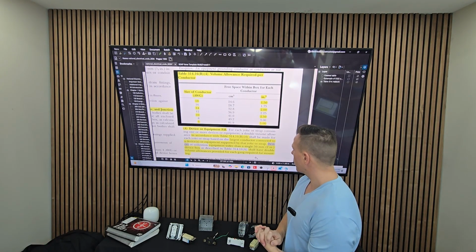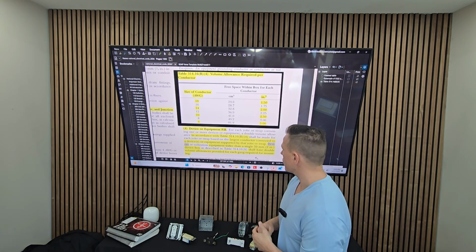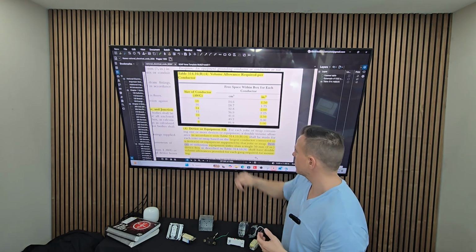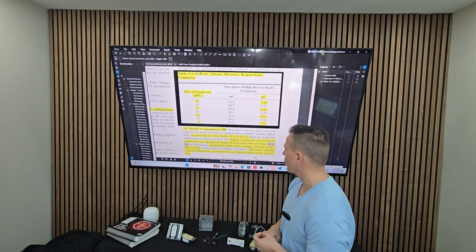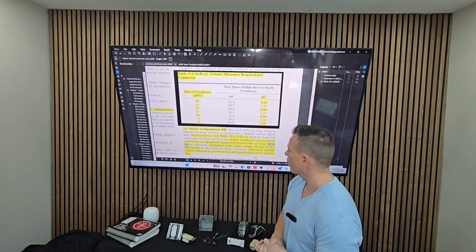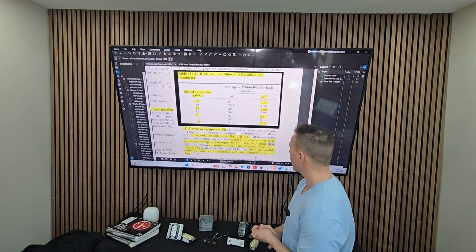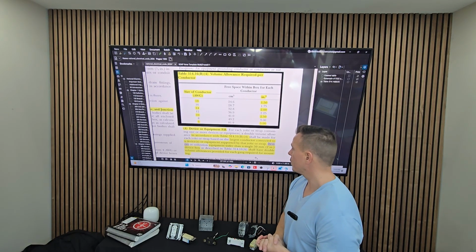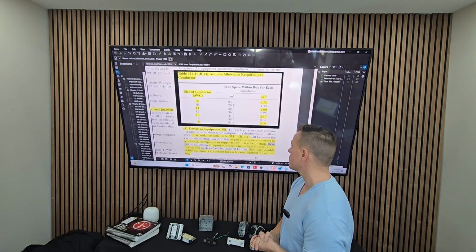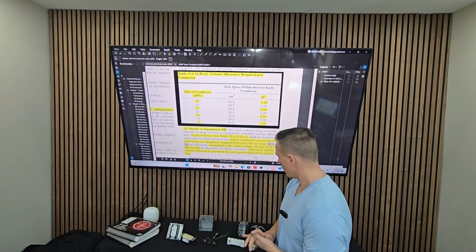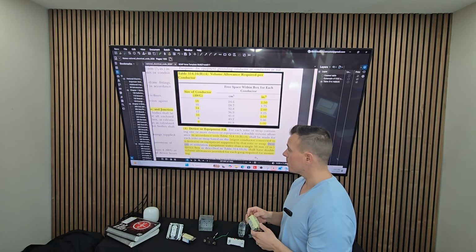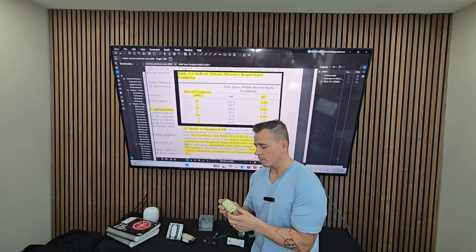And then they talk about each yoke or strap containing one or more devices or equipment, a double volume allowance in accordance with this table here, 314.16(B)(4), shall be made for each yoke or strap based on the largest conductor connected to that device or piece of equipment. All right, so I'm going to try and make this sound real simple, because it is simple once you understand it.